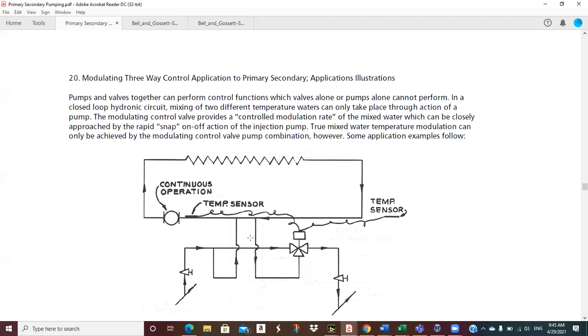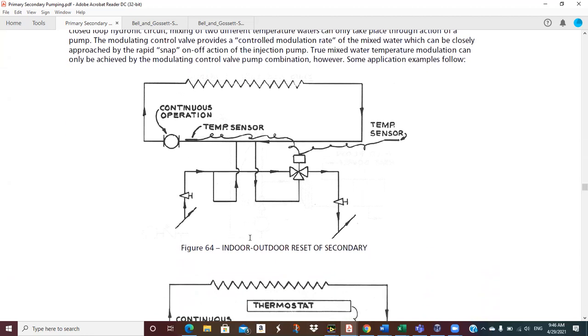Let's see, modulating three-way control application to primary, secondary. So we just have some applications here. Really good for temperature reset. So, usually we show these two bulbs. When you see the double bulb, this is in the outside air. This is, I guess, on the water that we're circulating. You got some sort of a schedule programmed in this thing. This valve modulates to give you the proper water temperature based on outside air.